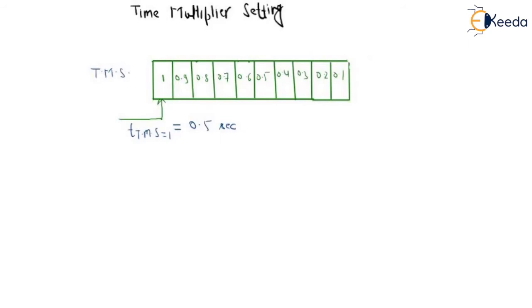So we know the formula: TMS required is equal to T required upon T of TMS equal to 1. This value is constant because this will be given when you purchase the relay. So T of TMS is equal to constant.